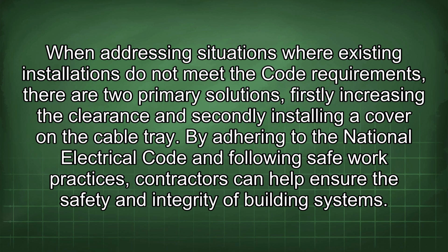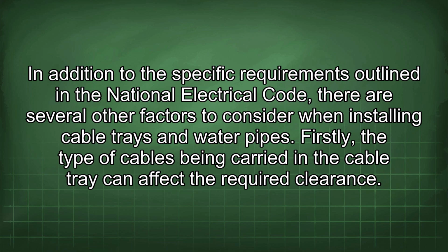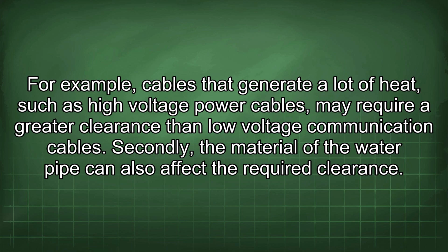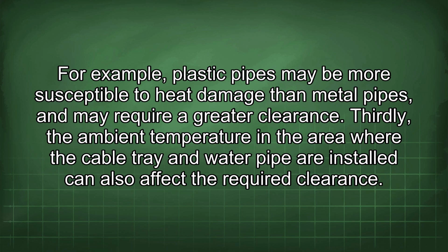of building systems. In addition to the specific requirements outlined in the National Electrical Code, there are several other factors to consider when installing cable trays and water pipes. Firstly, the type of cables being carried in the cable tray can affect the required clearance. For example, cables that generate a lot of heat, such as high-voltage power cables, may require a greater clearance than low-voltage communication cables. Secondly, the material of the water pipe can also affect the required clearance. For example, plastic pipes may be more susceptible to heat damage than metal pipes, and may require a greater clearance.